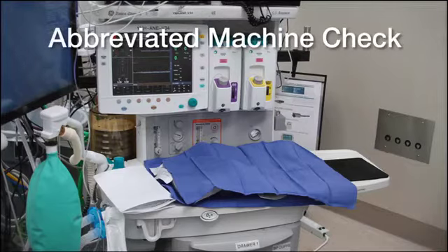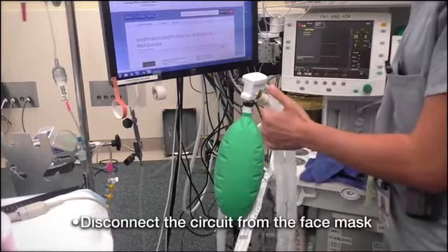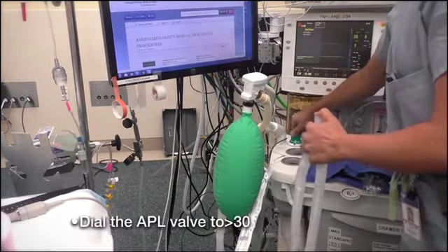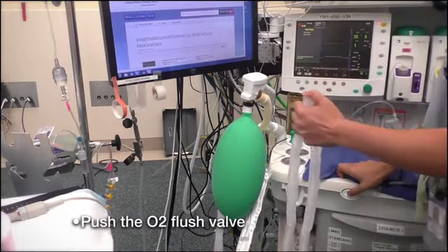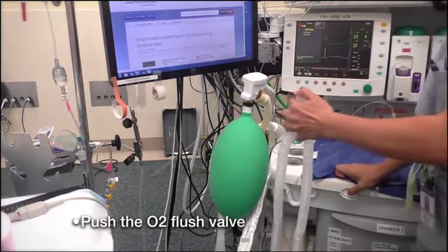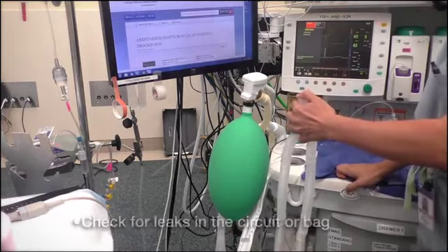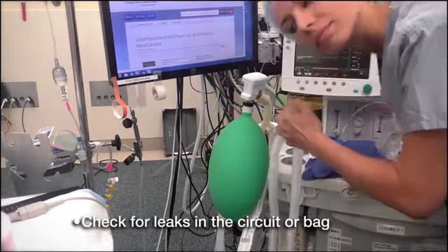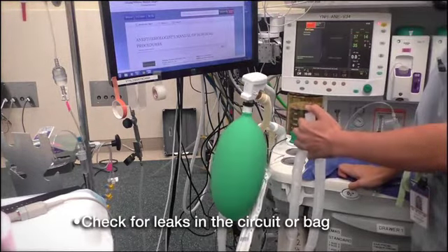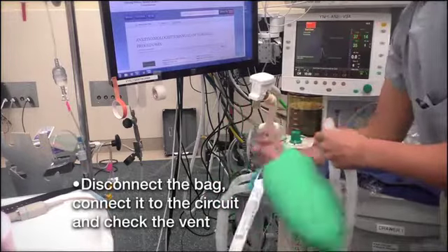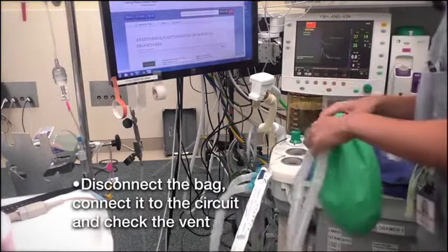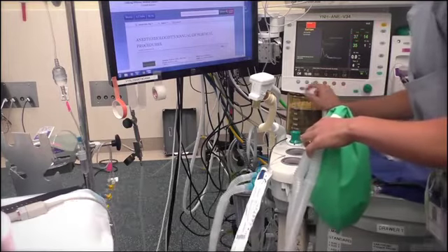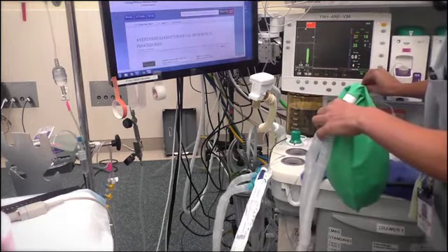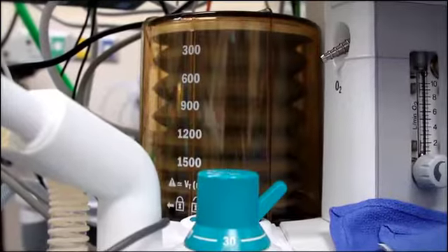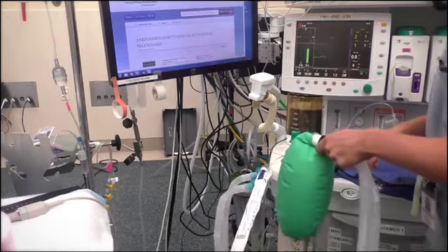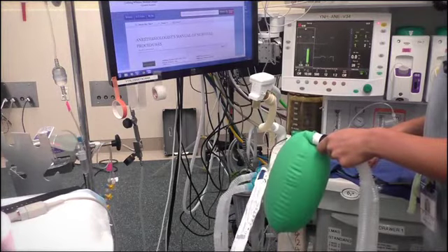Abbreviated machine check. Disconnect the circuit from the face mask. Dial the adjustable pressure limiting valve, or APL, valve past 30 centimeters of water. Occlude the circuit. Push the O2 flush valve until the bag expands and listen and feel for any leaks in the circuit or bag. The high pressure alarm should sound. Next, disconnect the bag from the arm and attach it to the circuit. Dial the O2 flows up and then switch the vent on. Make sure the bellows fully rise and fall. Make sure there's enough oxygen pressure from the main source and the O2 tank.